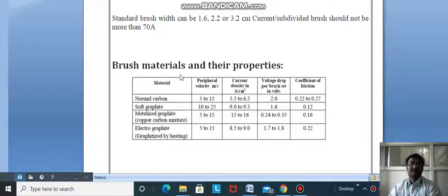Brush materials and properties: Normal carbon has peripheral velocity 5-15, current density 5.5-6.5, voltage drop 2, coefficient of friction 0.22-0.27. Metalized graphite (copper-carbon mixture): 5-15, 15-16, 0.24-0.35, 0.16. Electro-graphite: 5-15, 8.5-9, 1.7-1.8, 0.22. These are the different materials.